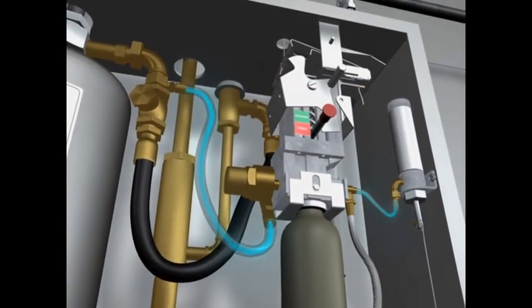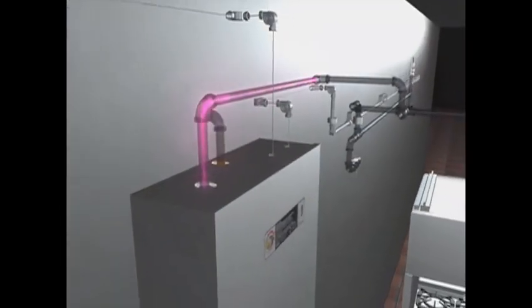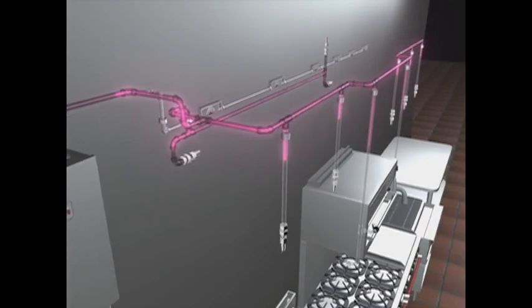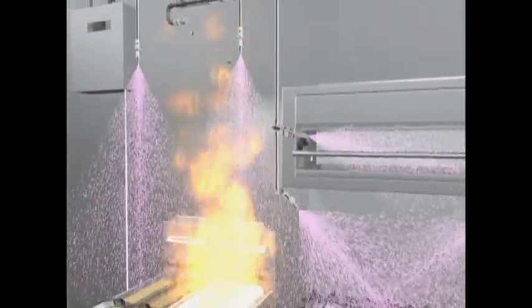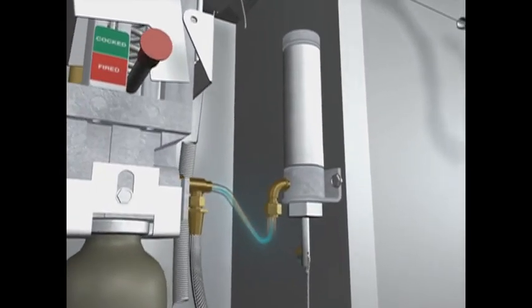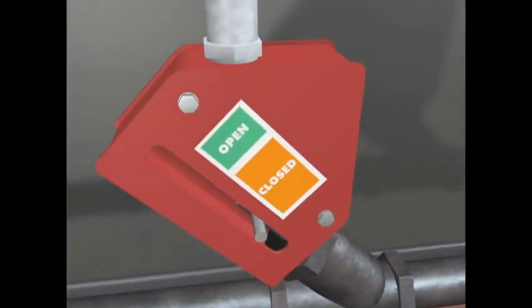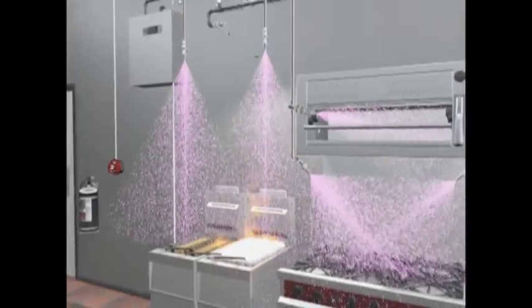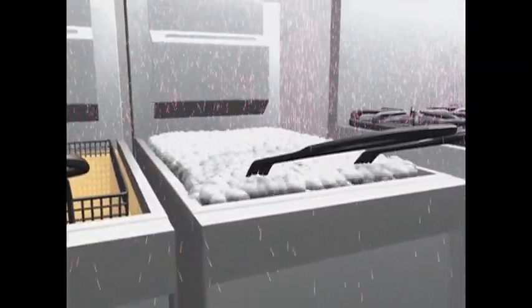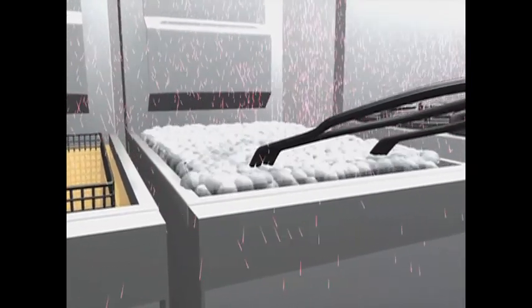The compressed gas pressurizes the PRX agent tank and discharges Ansul PRX wet chemical agent throughout the system, rapidly knocking down the flames. Simultaneously, an air cylinder is pressurized, tripping the Ansul mechanical gas shutoff valve. The discharged chemical reacts with the hot grease to form a vapor-securing blanket to help prevent fire reflashes.